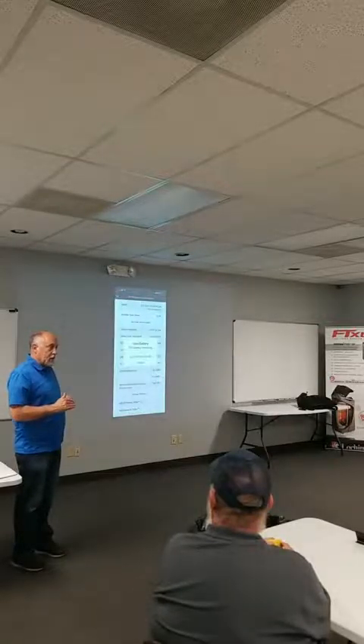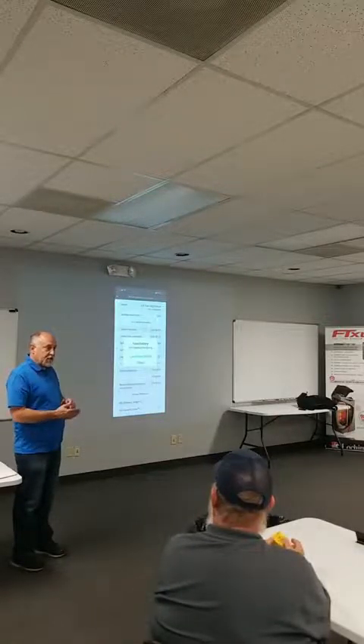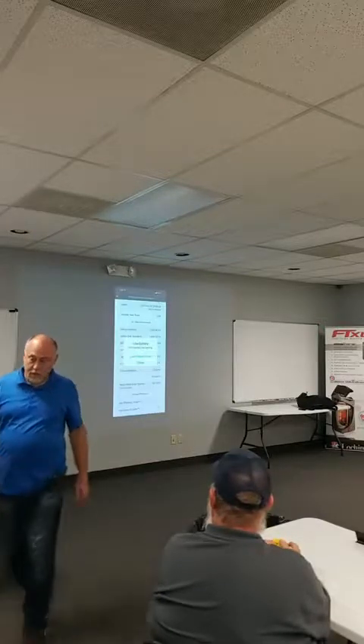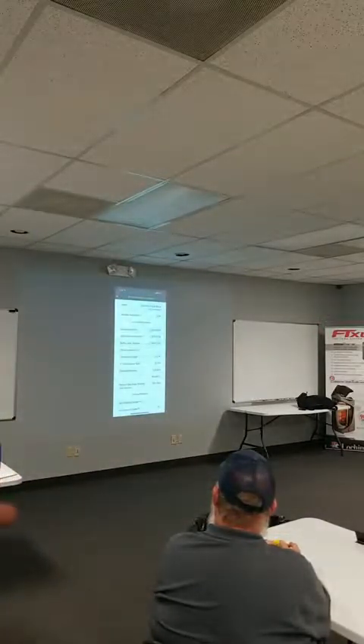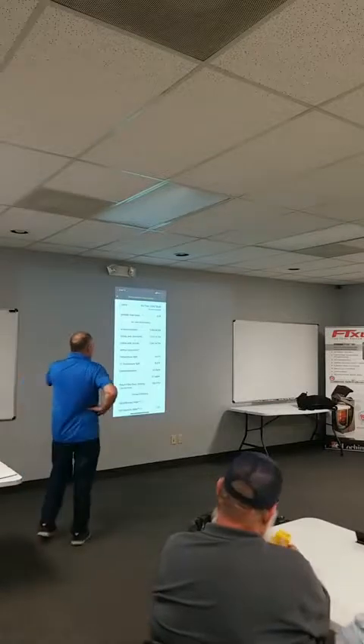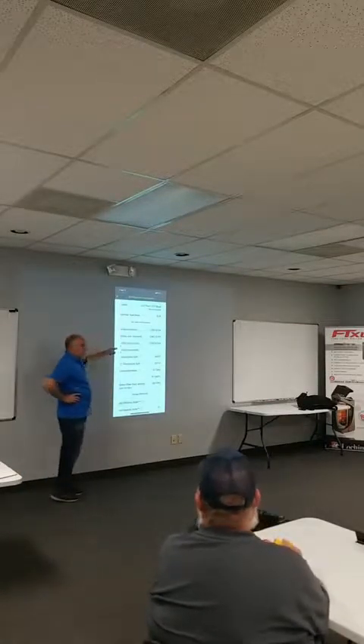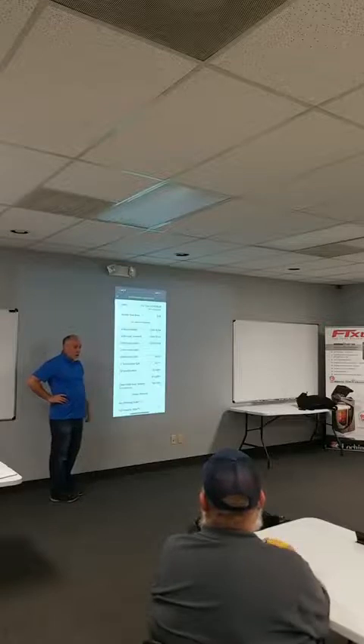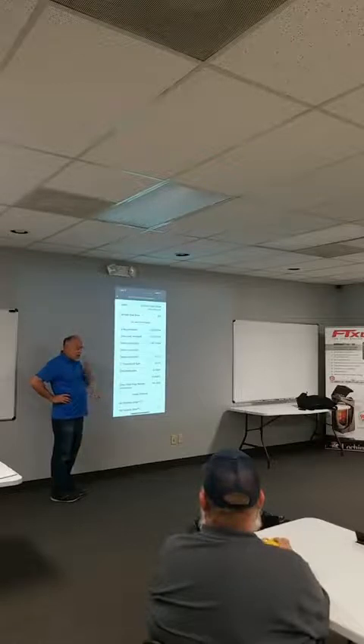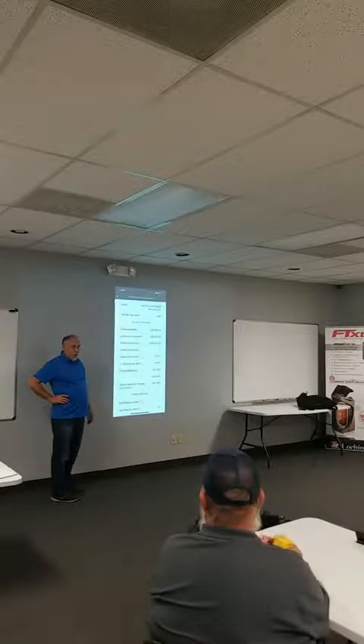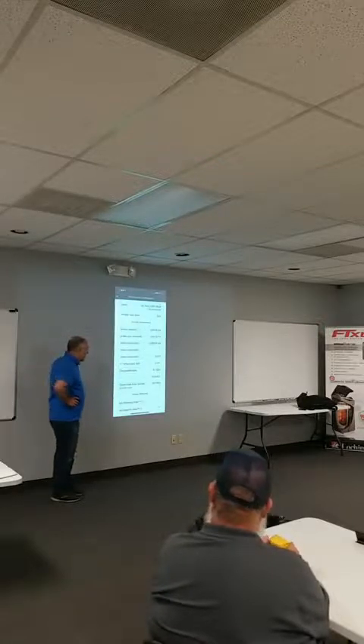So an ECM will move a constant mass flow. A PSC is a variable mass flow device, right? So two different motors. A lot of times what you'll see is your ECM, when it's hot and humid, if it's set for 1200 CFM, it might be moving 1400 CFM of actual air to get the correct standard air. And your PSC motor will be moving 1400 actual CFM. And you can leave it there because once the air cools back down, it's going to be in the right range, right? So you need to just watch standard and actual CFM when you're doing the air balancing.